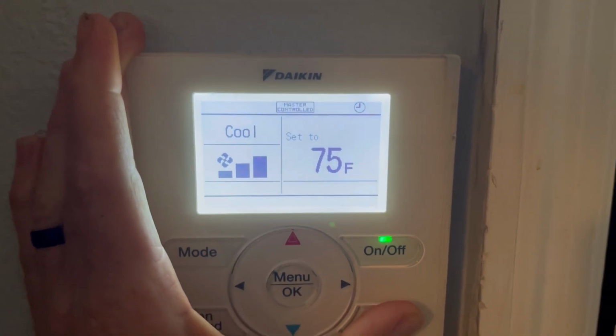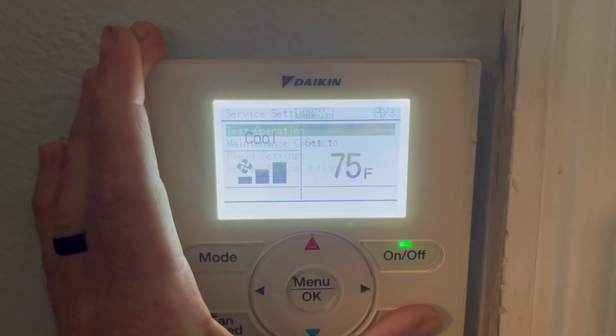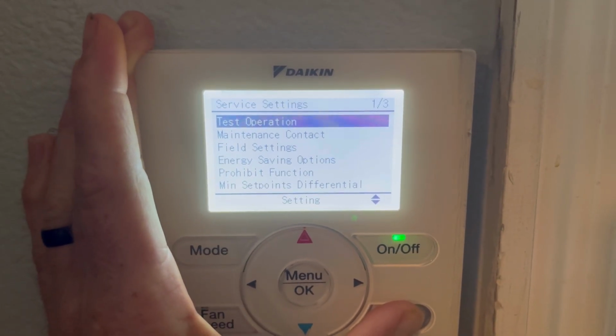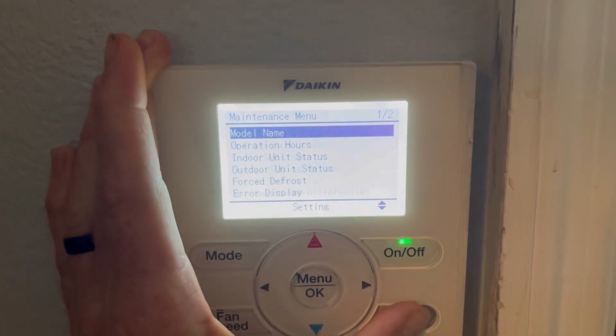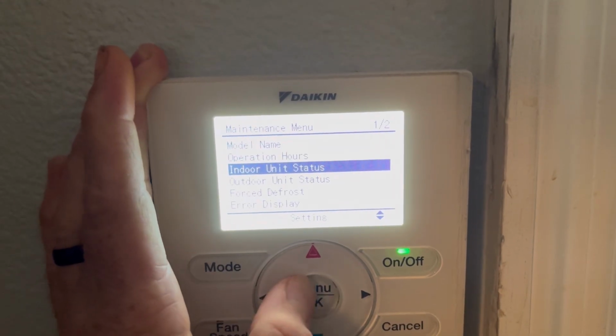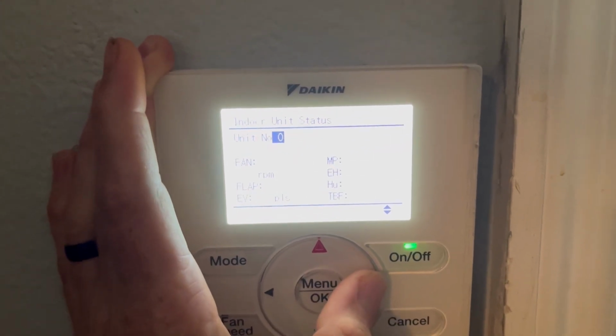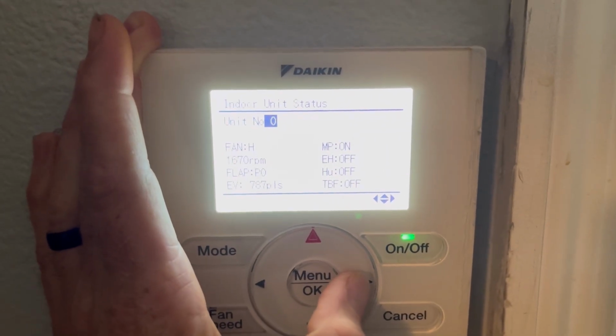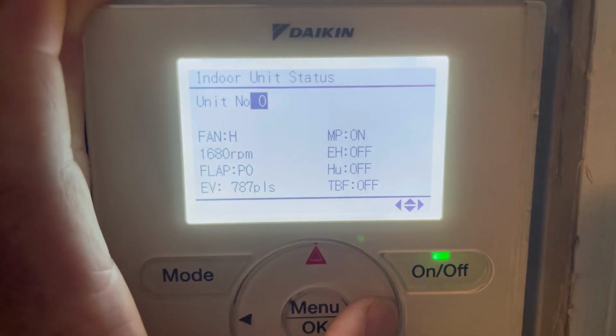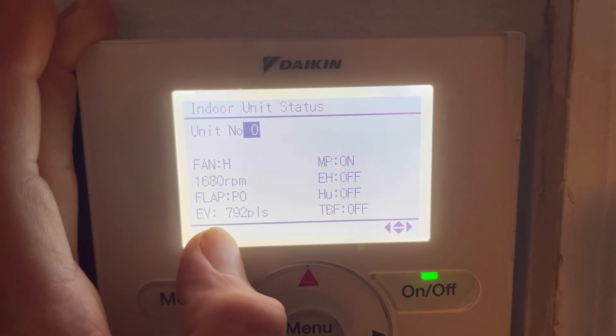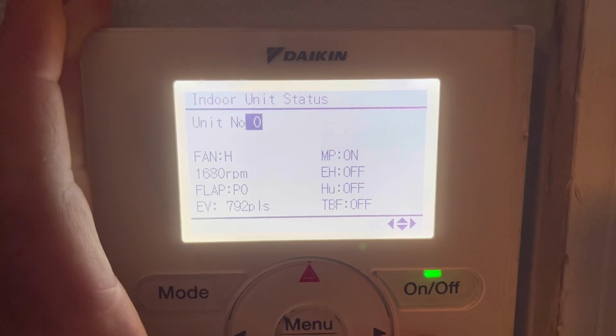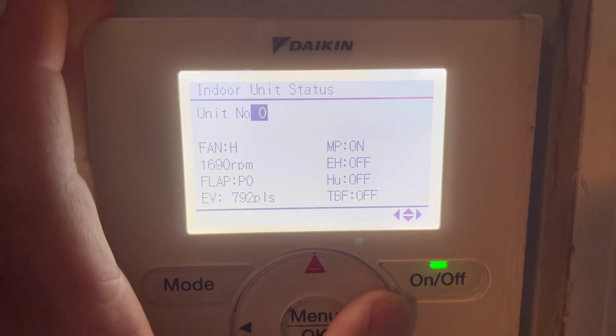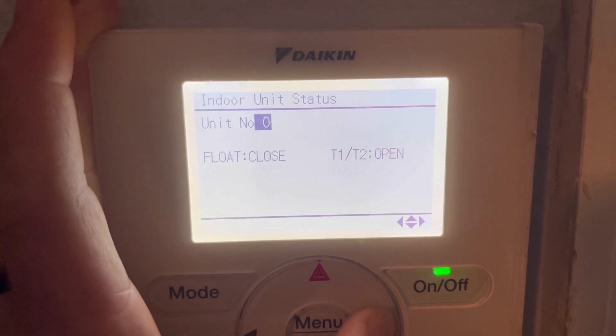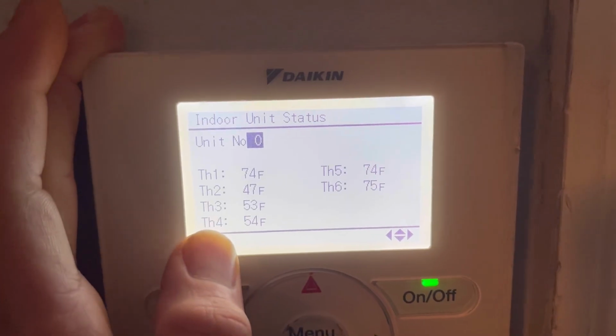Well, if I'm using them, again, hold down the cancel button for 5 seconds, hold down the cancel button again for 5 seconds. I'm using this when I'm troubleshooting a unit and I'm making changes. I just changed the expansion valve and I want to turn it on, but I don't have time to go back to the roof to look at the service checker data. Well, I can go here and look, my pulses are climbing. I'm not going to find a faster way to refresh the data to see what's actually happening with my system than using the BRC controller that is here in the room.